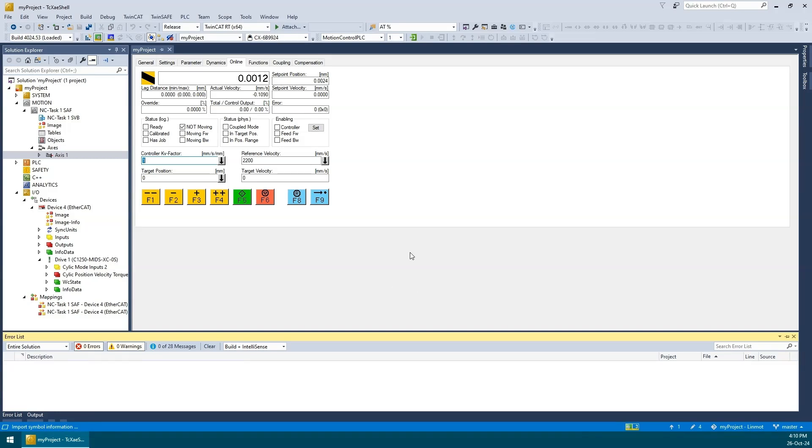Hit OK to put the PLC into run mode. And we're all set. Looks like I'm getting some position feedback from the servo. This servo has an incremental encoder, so it does not give absolute position. On power up, it will report the current position as zero.